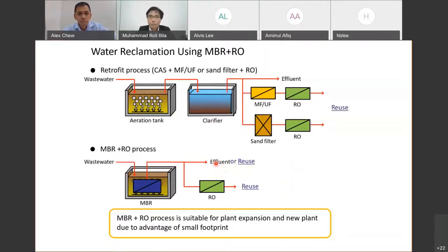Okay. So you see here that if you use activated sludge, you have an aeration tank and a clarifier. To be able to reuse, you either need to go first to a sand filter and RO to meet the quality, or you will need a pre-treatment for your RO using microfiltration and ultrafiltration, followed by RO. So if we have MBR, depending on the purpose, we can directly use the effluent if the quality meets the requirement.